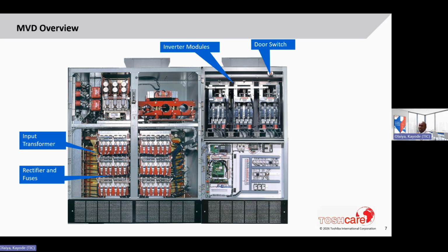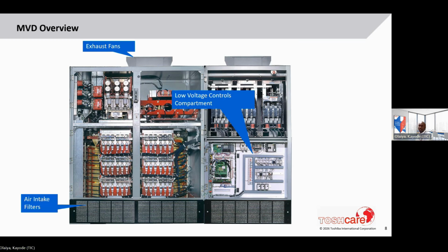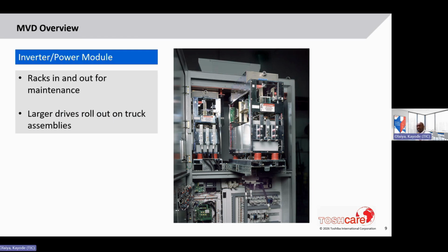And there is a door switch for safety to make sure that power is disconnected or de-energized when the power module doors are open. We have the exhaust fans, which pull air in from the bottom through those air intake filters and exhaust at the top. And then the low voltage compartment, which we also call the control section, has all the boards and controls for the drive. Then finally, narrowing down to the power modules, they rack in and out easily for maintenance. And for the bigger drives, we have a rollout truck assembly specifically for rolling out those modules, which can be quite heavy.